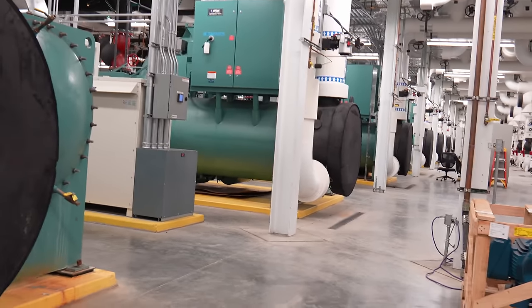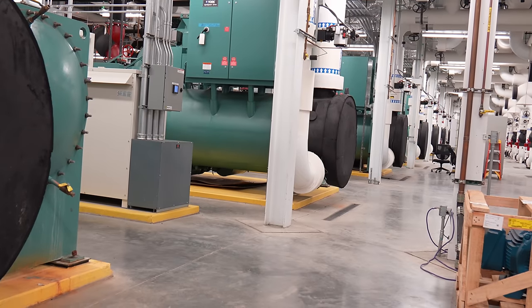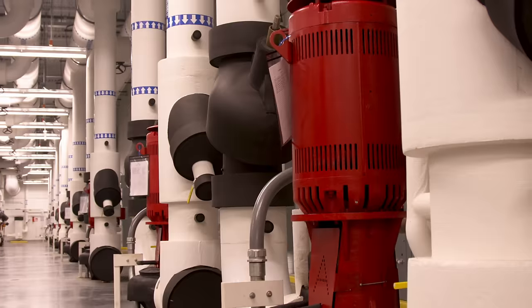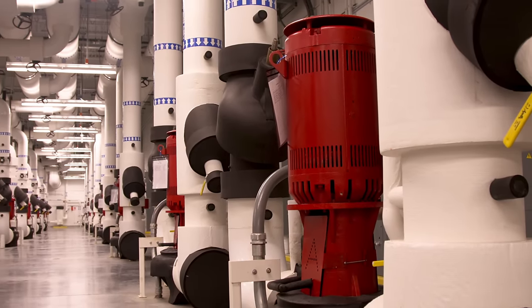There's also a million-gallon water tank in one corner and another million-gallon tank for the other phase — these act like cold batteries. Power is expensive during peak daytime hours, but cheap at night. So at night, when efficiency is excellent, they chill down a million gallons of water. During peak times, instead of running all the centrifugal chillers, they draw on that cold water to help cool the system, using the thermal storage as a heat transfer medium. It's not just 'run until it's cool' — it's about maximum thermal efficiency.